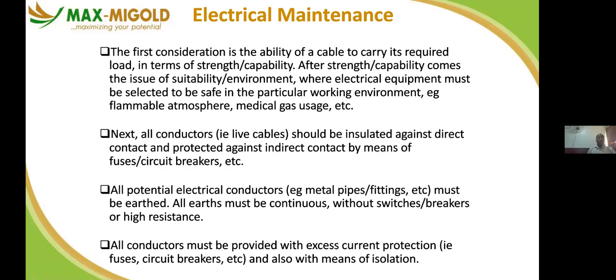So in electrical maintenance, a number of factors also need to be considered. The first thing to be considered is the ability of the cable to carry its required load. As a rated voltage, you have 2.5 mm, we have 4 mm, we have 1.5, 1 mm, 16 mm, and so on. But because of cost, people want to cut costs. They use 1.5 instead of 2.5 mm, and they will be used for their oven or electric cooker. Within a short period of time, that wire gets melted and the whole installation is compromised.